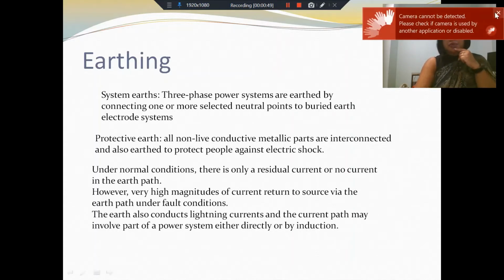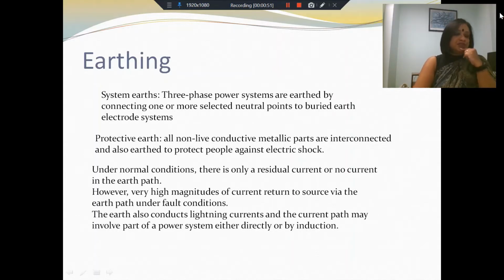And then there is a protective earth, which encompasses the entire earthing system. All non-live conducting parts, metallic parts, are interconnected. They're connected to each other to raise them to the same potential, and then they are earthed. The reason is that we want to protect people from electric shock. So one is the system earth, and then there is the protective earth. We will see how we maintain and interconnect them.